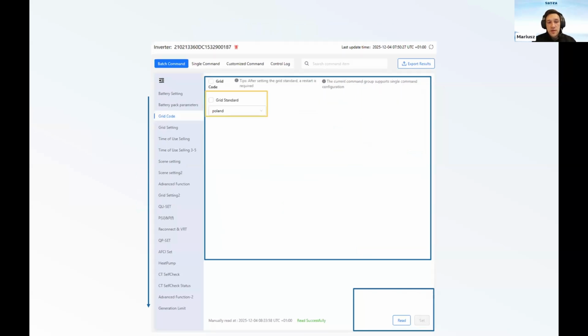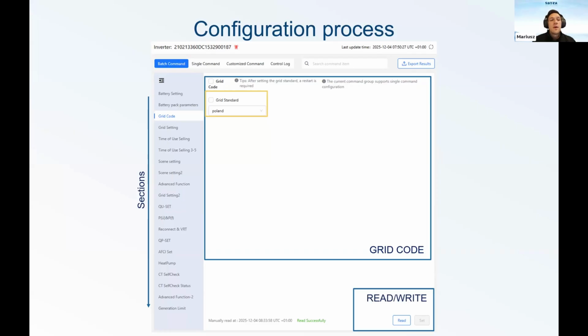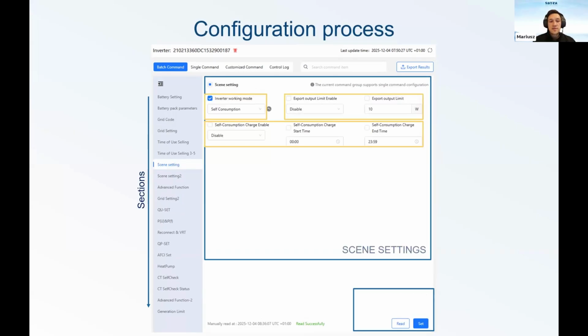Then we set up the grid code. There are different grid codes for the whole of Europe. I think you are familiar with it. Then we can set up the scene settings. The scene settings define the working mode of the inverter. I chose self-consumption because it's the most commonly used solution and working mode. We can export the power output of the inverter to the grid, and we can limit the export to the grid. We can set up the self-consumption charge enable and when we want to charge the batteries. For example, if we have two tariffs and one is much cheaper than the other, we can charge during the winter from the low price tariff and use it at the high price tariff.